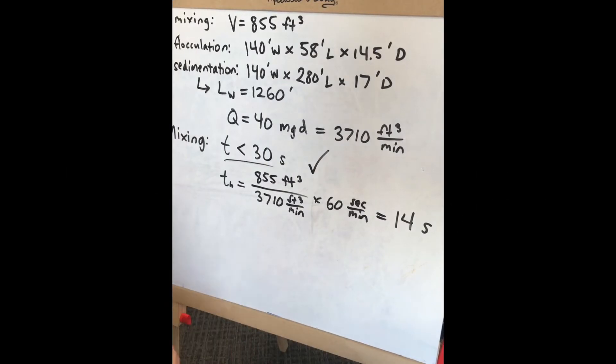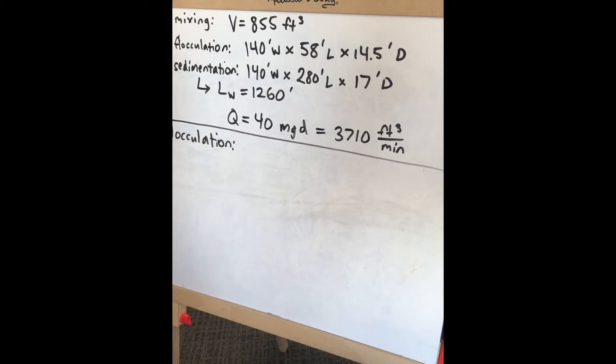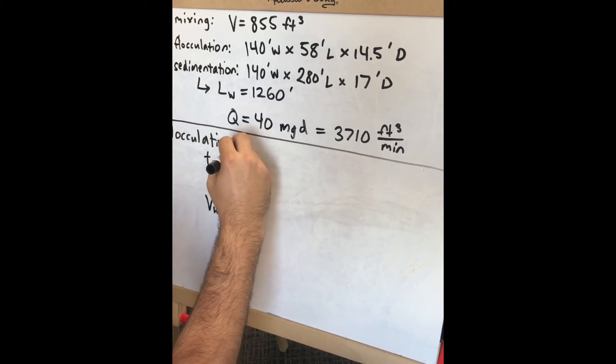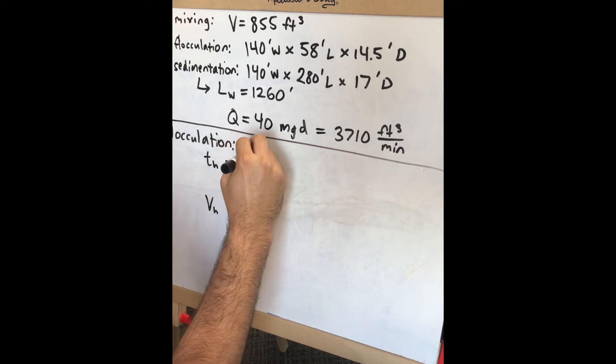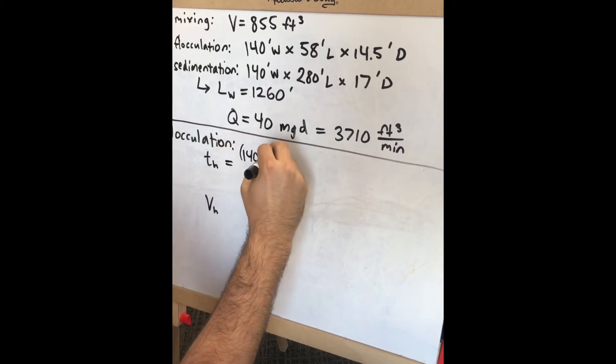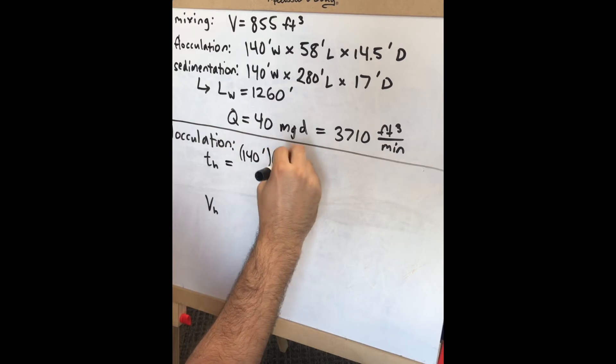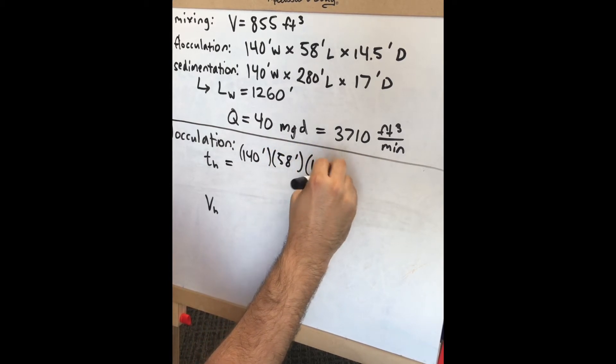For the flocculation basin, we need to examine detention time and horizontal velocity, as these are specified in the design criteria. For detention time, calculate the volume: 140 feet times 58 feet times 14.5 feet.